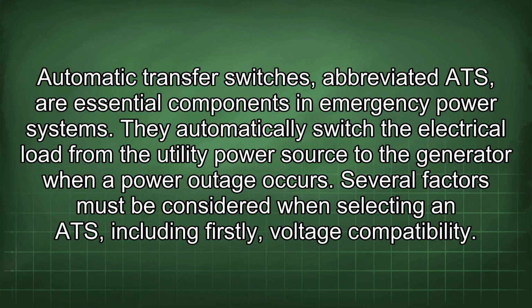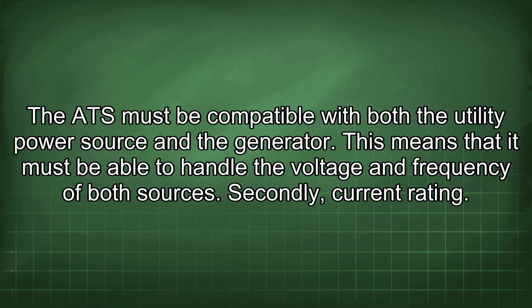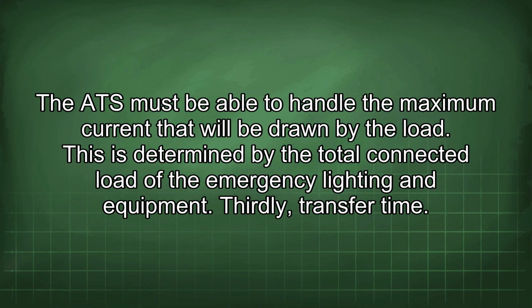Several factors must be considered when selecting an ATS, including, firstly, voltage compatibility. The ATS must be compatible with both the utility power source and the generator. This means that it must be able to handle the voltage and frequency of both sources. Secondly, current rating. The ATS must be able to handle the maximum current that will be drawn by the load. This is determined by the total connected load of the emergency lighting and equipment.